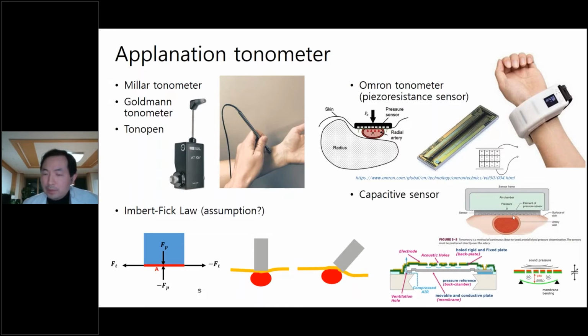small array of plungers recruited to flatten the artery during the measurement session, the number of the recruited plungers will be proportional to the internal pressure of the artery. So we can estimate the internal pressure of the radial artery. However, this device requires calibration. So reproducible calibration is the most important part of this kind of applanation tonometer type device.